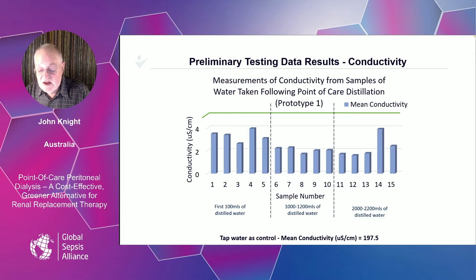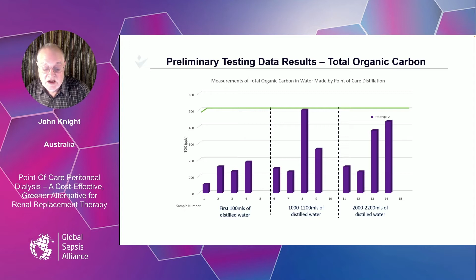The second test we use is total organic carbon, a very sensitive assay that will detect any carbon-based life forms in the distiller fluid. Here, the British Pharmacopoeia standard is less than 500 parts per billion, and again, as you can see, we're well within that range.